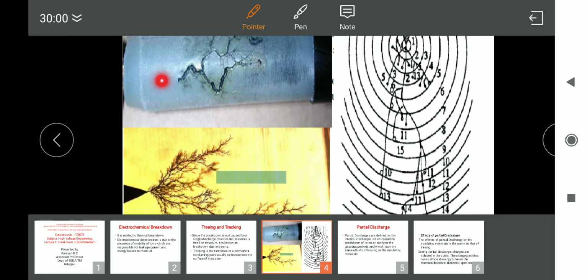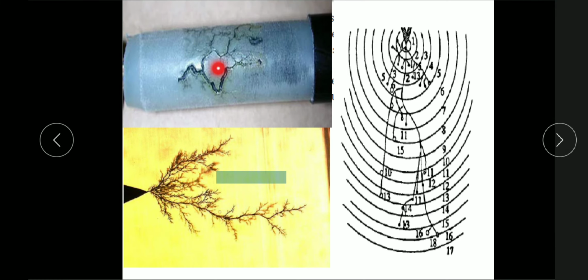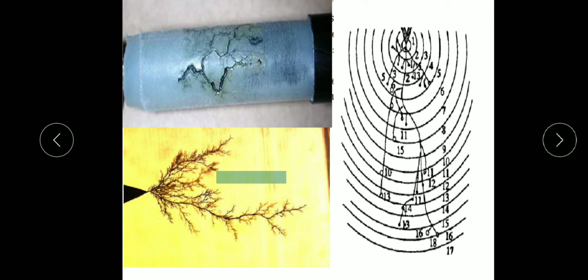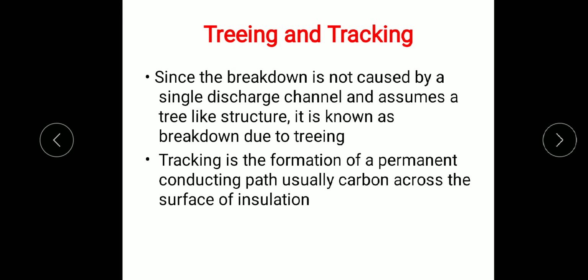When you apply higher voltages, it will break like this. The weaker section will collapse first. This is the weaker section in a solid material, compared to the center part. When you apply high voltages, it will collapse or deteriorate. That is what the definition is: the breakdown is not caused by a single discharge channel and assumes a tree-like structure. That's why it is called a tree.